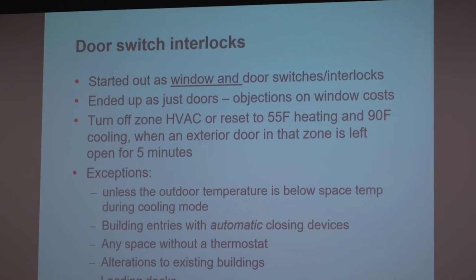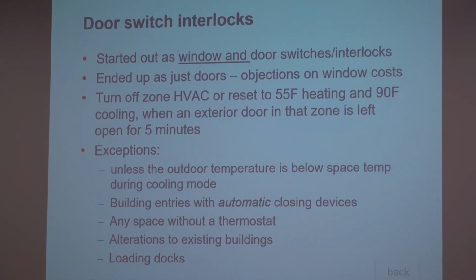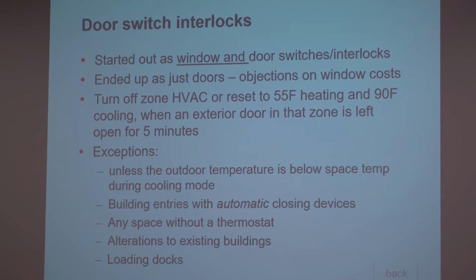I mentioned this morning, for those of you who were here, one of the things that really is a way that buildings, envelopes, and the mechanical equipment need to work better is on the interface between operable windows and doors and the air conditioning system. The switches for operable windows are more expensive to implement, and so while it might have started out as full fenestration, whether it's a window or a door, it now has to, well, I guess doors aren't always fenestration. The glass ones are fenestration, but otherwise it doesn't matter. So it ended up being that we just have the door switches, and there are exceptions with automatic closing devices, unconditioned spaces, loading docks, etc. You can change those, but this is another place where 90.1 and IECC deviate. I don't believe that this is in IECC, unless it's in a different chapter and I didn't find it, which could be.